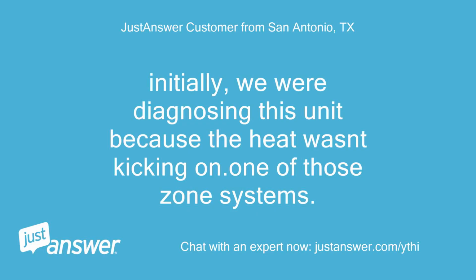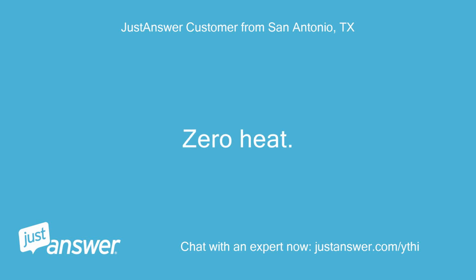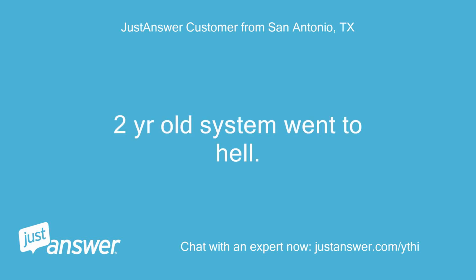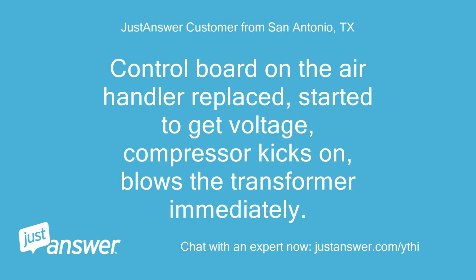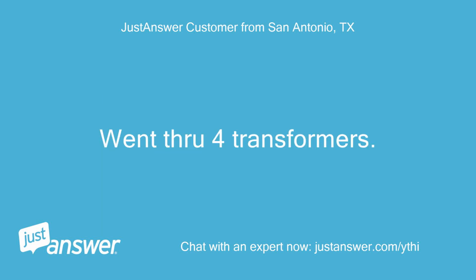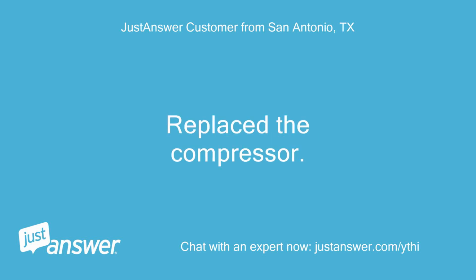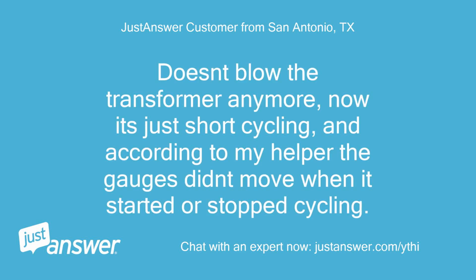Initially, we were diagnosing this unit because the heat wasn't kicking on. One of those zone systems. Zero heat. Nothing. 2 year old system went to hell. Control board on the air handler replaced, started to get voltage, compressor kicks on, blows the transformer immediately. Went through 4 transformers. Replaced the compressor. Doesn't blow the transformer anymore, now it's just short cycling, and according to my helper the gauges didn't move when it started or stopped cycling.